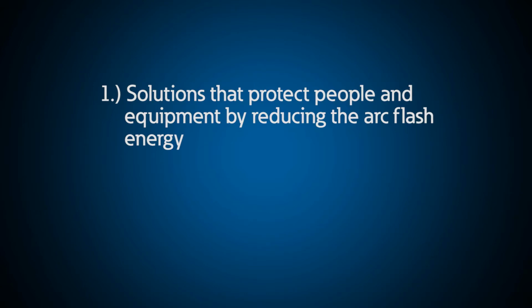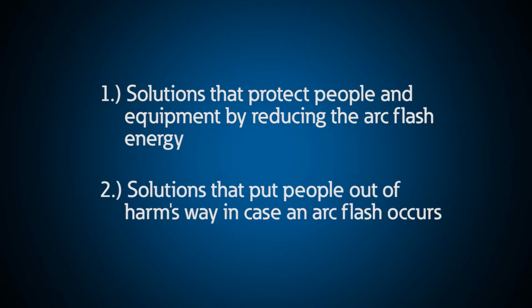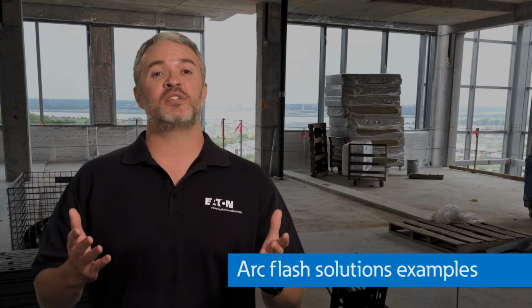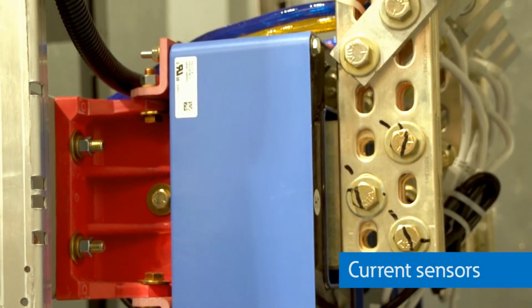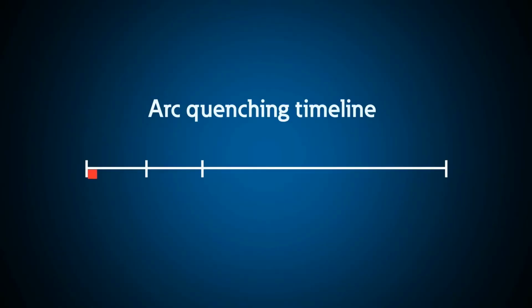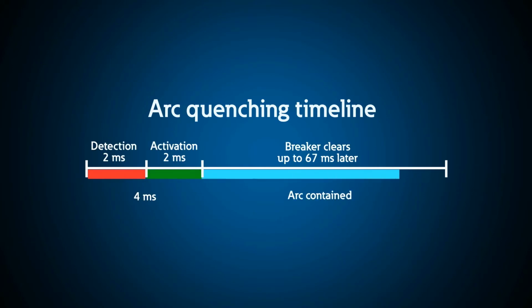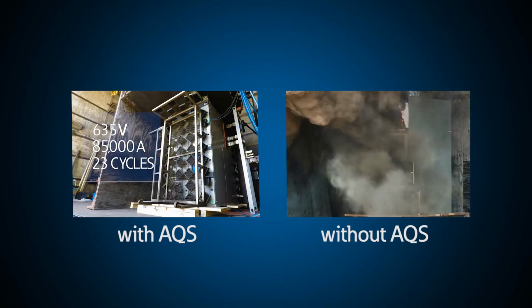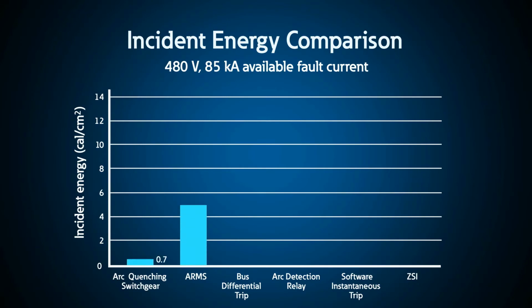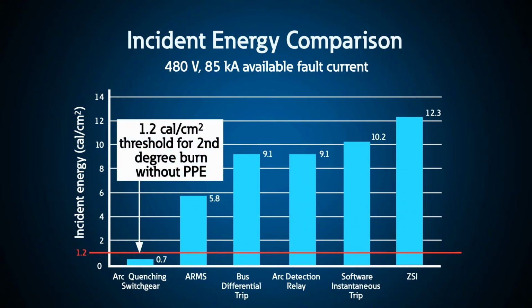There are essentially two main categories of arc flash solutions. One, the solutions that protect people and equipment by reducing the arc flash energy, and two, solutions that put people out of harm's way in case an arc flash occurs. Here are some examples that we think you, as a contractor in a healthcare environment, might want to know about. Arc quenching switchgear is revolutionizing the industry by creating a solution that not only protects your gear, but anyone standing near your switchgear during an arc flash event. Basically, arc quenching switchgear uses a system of light sensors, current sensors, and this device to create a parallel arc during an uncontrolled arc in the switchgear to provide an alternate and controlled path for fault current until an upstream device can clear the fault. During this scenario, your people and equipment are protected because the arc quenching switchgear reacts so fast and responds before the dangerous pressure wave can build up. Think of this device as an arc flash airbag for your electrical system.